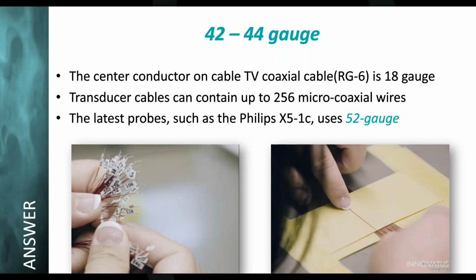So that's what they look like. They're 42 to 44 gauge, but we actually have the new one. You can see Philips has a new probe. They're using 52 gauge wire. And that was one of those oh crap moments when we opened up the first one that we saw. We're like, oh my God, why did they go to this wire? Now keep in mind, these are all coaxials. So you have a shield and a center conductor. There's 2 conductors within that coaxial cable.